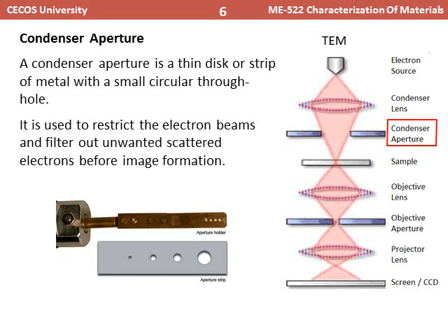Next comes the condenser aperture, which is a thin strip with small circular holes of various sizes. The purpose of the condenser aperture is to restrict the electron beam and filter out unwanted scattered electrons before image formation or before the beam passes through the sample.